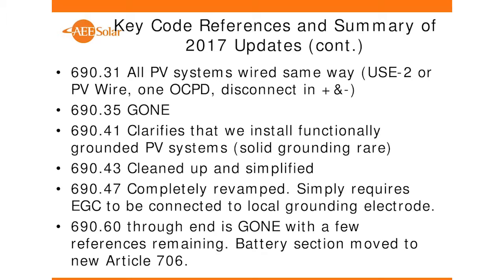And solid grounded systems are extremely rare. It's solid grounded systems where we have a wire connected to our conductor only allowed for 1 and 2 string circuits or 1 and 2 source circuit arrays that are completely separate from buildings. So you're not allowed to bring those conductors anywhere near a building or in a building. And those are the only ones that are allowed to not have ground fault detection on them. So if you have a solidly grounded system, it's allowed to not have ground fault detection on it. But it also can't have anything to do with the building.